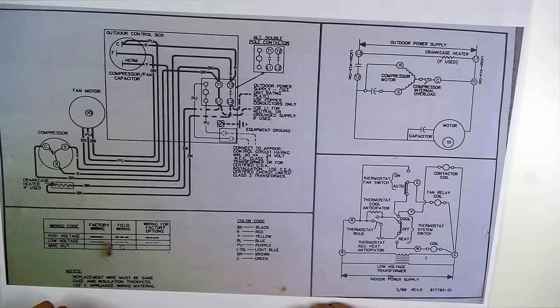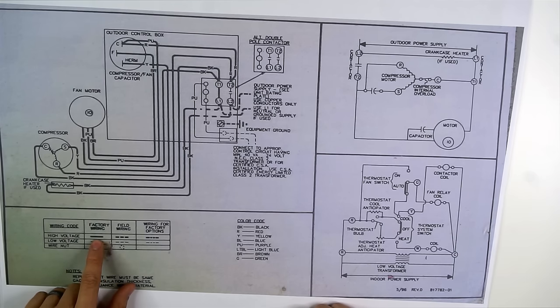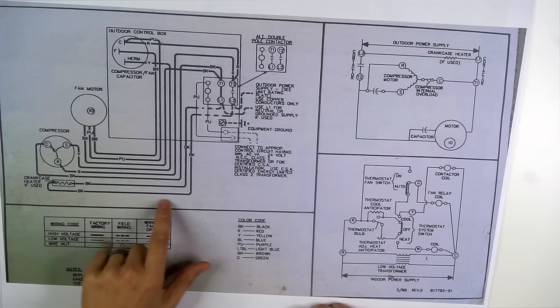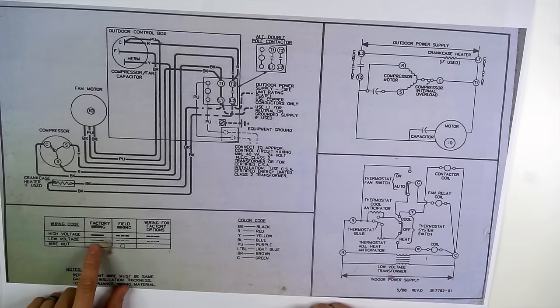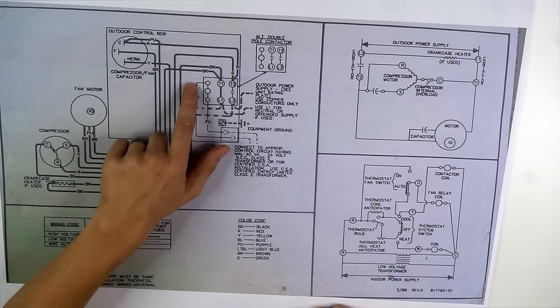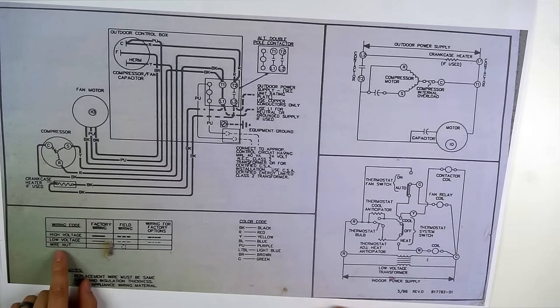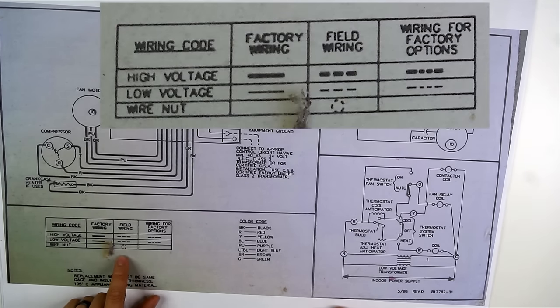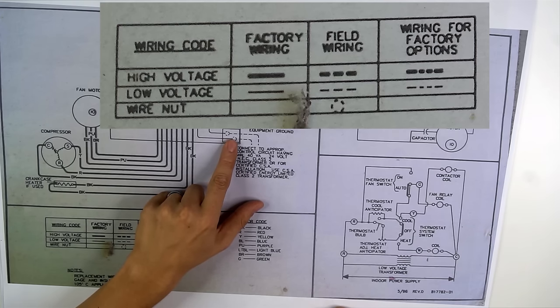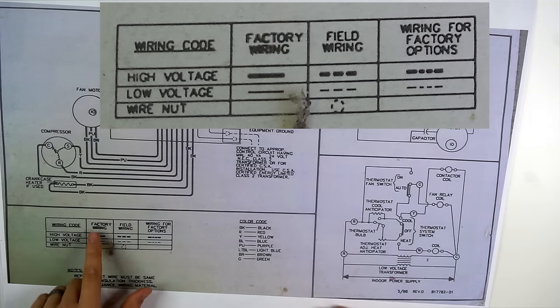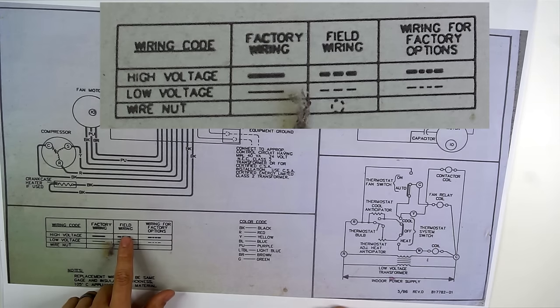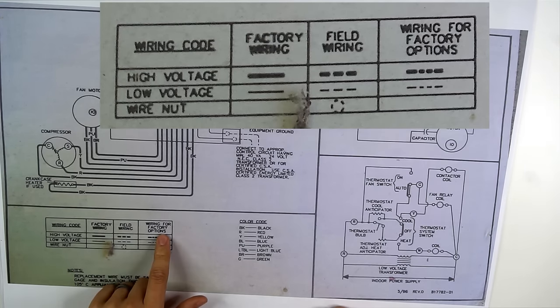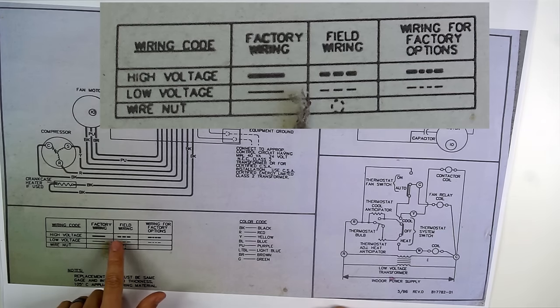You've got your wiring codes. High voltage wires are going to be thick bold lines, like right here. The thinner lines are going to be our low voltage lines, like right over here going to the contactor coil. A wire nut will be symbolized as a circle made out of dashed lines — there are only two of those wire nuts in the whole diagram. The second column says field wiring and the third says wiring for factory options, both shown as dashed lines.